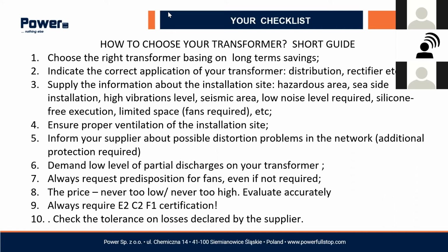The next point is really very important. You have to give all possible information to your supplier about the installation site. Is it a hazardous area? Is it an area with a lot of dust, problems with humidity, or is your installation very close to the seaside, or is there a high level of vibration, or are you installing in a seismic area?